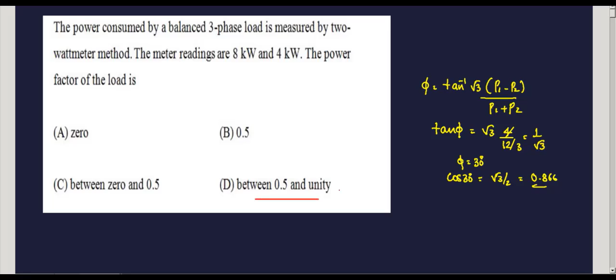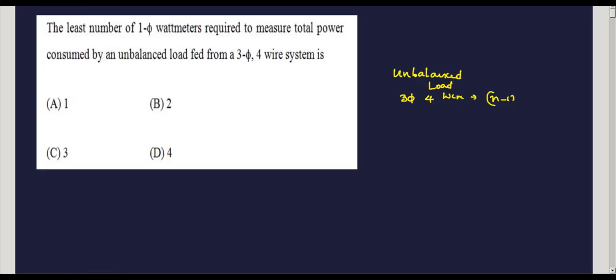Let's see the next question. The least number of single phase wattmeters required to measure total power of an unbalanced load. Let's note these points. For an unbalanced load on a 3-phase 4-wire system, you require n minus 1 wattmeters. Here n is the number of wires, 4, so 4 minus 1, 3 wattmeters. So for a 3-phase 4-wire unbalanced system you need 3 wattmeters. For a balanced 3-phase 4-wire system, only a single wattmeter is required.